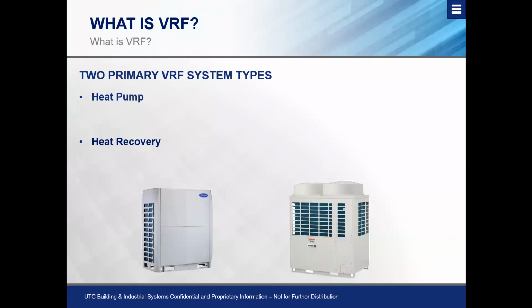So as we dive into VRF, there are two primary system types, and typically this is where the confusion comes in with VRF, is assuming that all VRF is heat recovery, when in fact, there are heat pump VRF systems. So first and foremost, with the heat pump, these are going to be traditional heat pump systems. So these are going to be units that can either heat or cool, but cannot give you that simultaneous heating and cooling that VRFs are typically associated with doing. So it's certainly important to make sure that you specify whether you want a heat pump or whether you're looking for that heat recovery with that simultaneous mode. So now we know what the heat pump is. We know that that's all heat or all cool, whether we have one unit or whether we have 25 units.